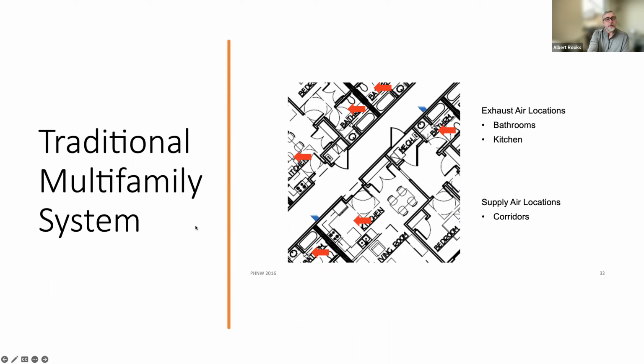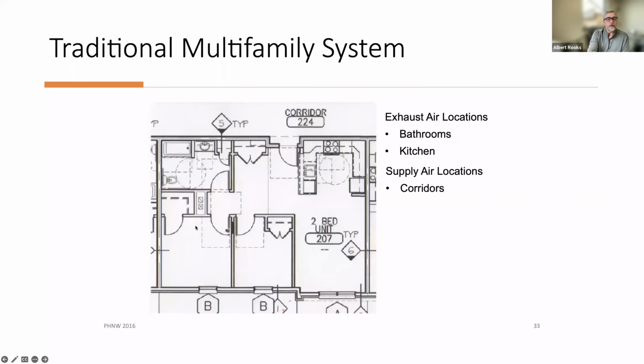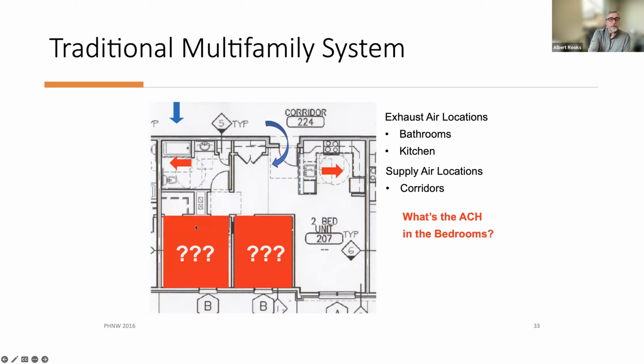Supply air in a pressurized corridor all comes into the corridor, and it's supposed to get pushed under the door into the unit, right? So we have positive pressure in the corridor and negative pressure in the unit, and that's how we ventilate. Conditions and effectiveness vary, but all the air shows up at the front on the corridor side and travels to the negative pressure zones, which are also typically right up there at the corridor side. They follow the path of least resistance, the red arrows.